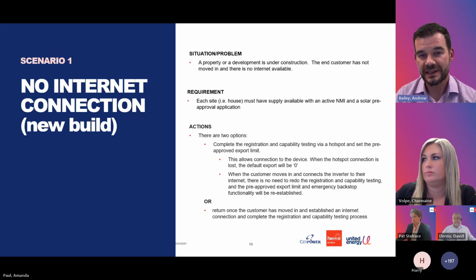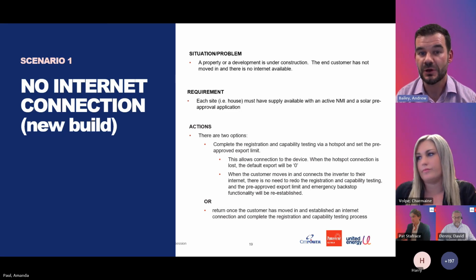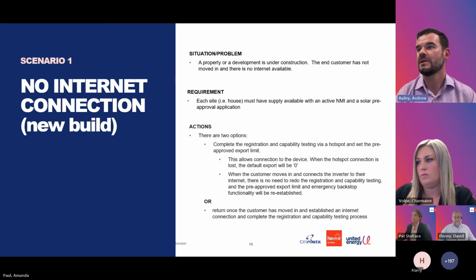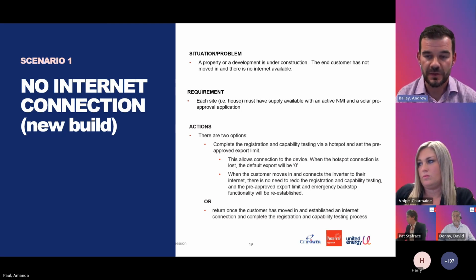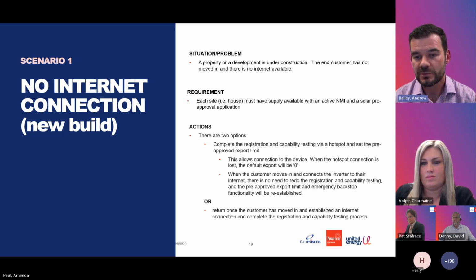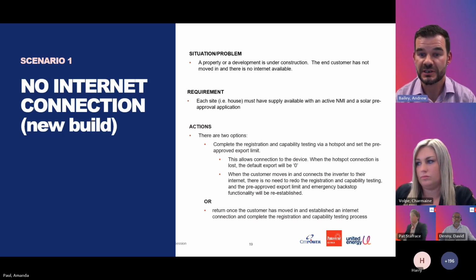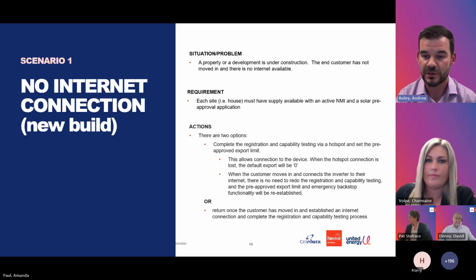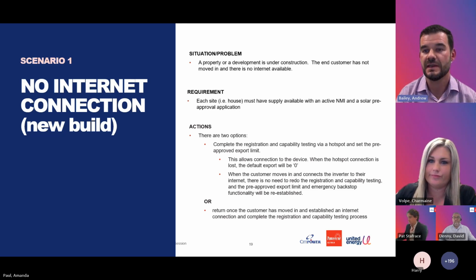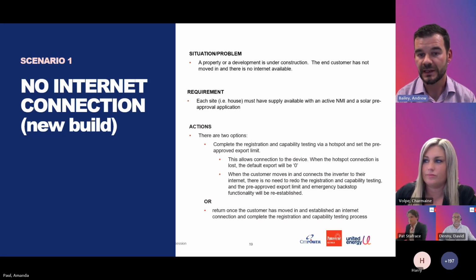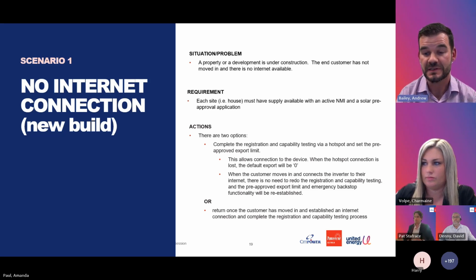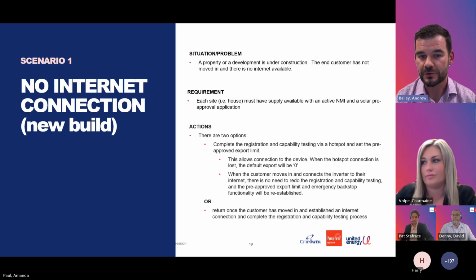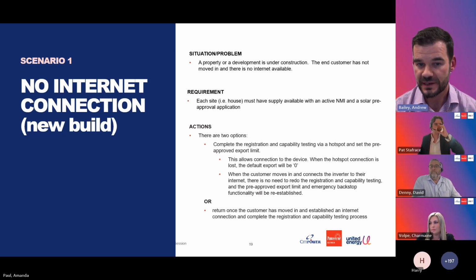Scenario 1: no internet connection. For example, if a property is under construction and there's no customer there yet, and no internet. The house must have a supply available with a NMI and a solar pre-approval application. There are two options: the registration and capability testing can be completed via a hotspot, and the pre-approved export limit can be set. When the hotspot goes away and the connection is lost, the default export will be 0. Later, when the customer moves in and connects the inverter to the internet, they will revert to the pre-approved export limit from before, and there should be no need for a second visit.